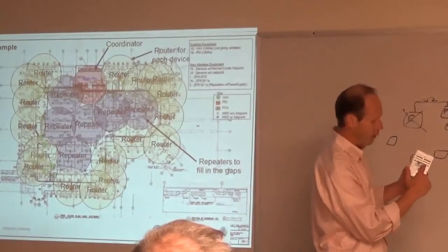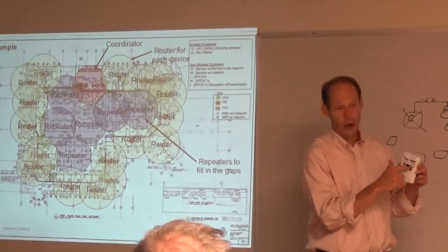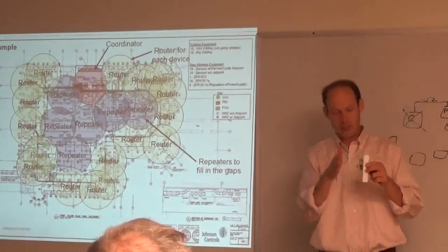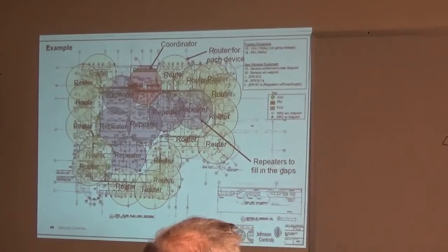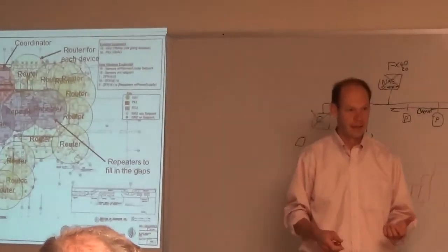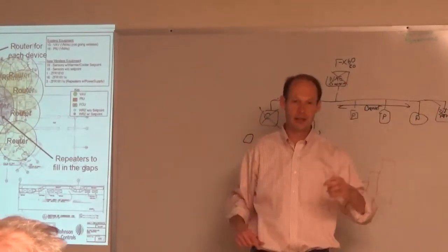There's a little switch in the back, power on. On the back of these guys you put a little white piece of paper. It shows whether I'm one-to-one, meaning I'm doing the WRZ-7860 communication, or full mesh, and it tells you what to do with the dip switches. As you can see, this one is a one-to-one application, so it shows what the dip switches mean. You mount them but don't turn them on, so they don't sit there panicking. If they have somebody to talk to, they know who they're talking to and go back to sleep.